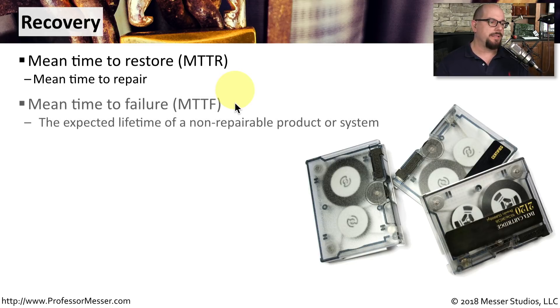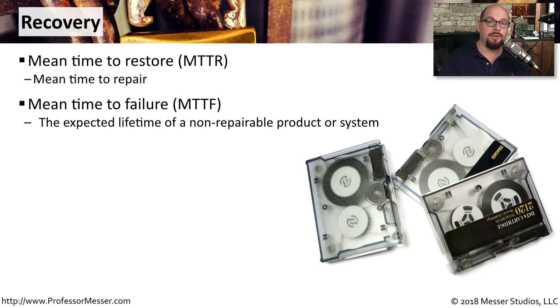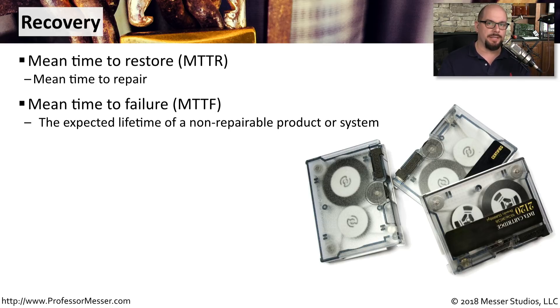That's a little bit different than a mean time to failure, or MTTF. With a mean time to failure, the system is not repairable — it's a system that must be replaced if there's a failure. So the MTTF might give you a reasonable idea of the lifetime expected for a particular product or a particular part that's in a system.